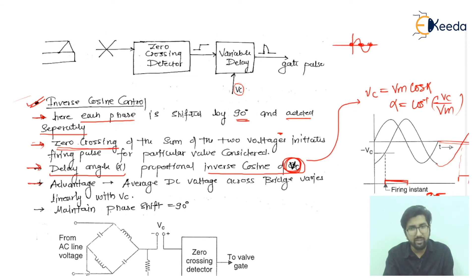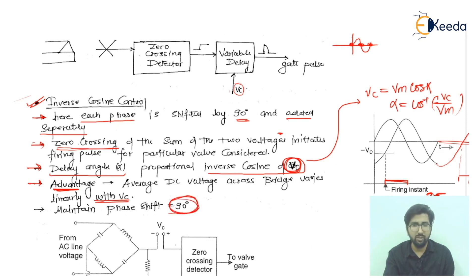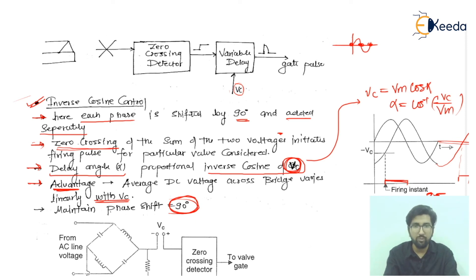The advantage of inverse cosine control is that the average DC voltage across the bridge varies linearly with Vc. It will vary linearly with Vc and ultimately maintain the phase shift by 90 degrees. The connection scheme has Vc plus/minus feeding into the zero crossing detector and then to the valve gate for firing the valve.